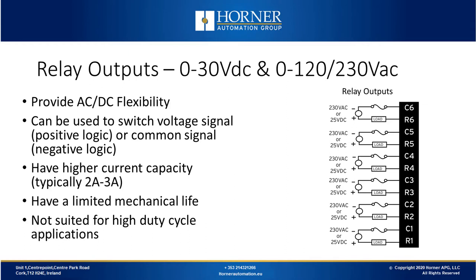Let's take a look at relay outputs. These can switch either the supply voltage or the common signal. They're usable with both positive logic and negative logic type systems, and they have higher current carrying capacity. In exchange for that, they have a limited mechanical life and are not suited for high-duty cycle applications.